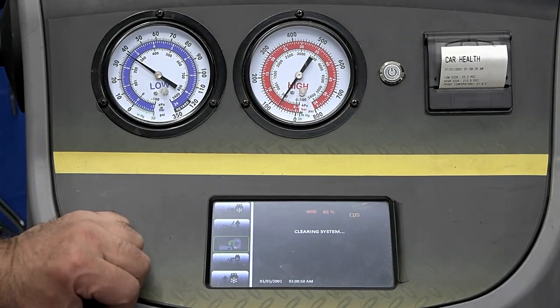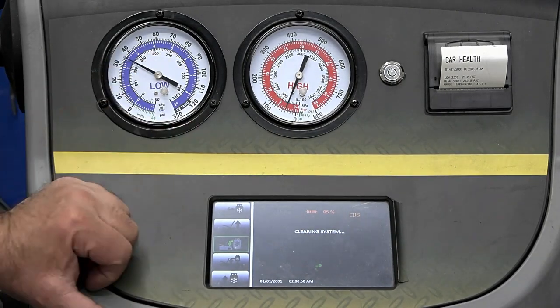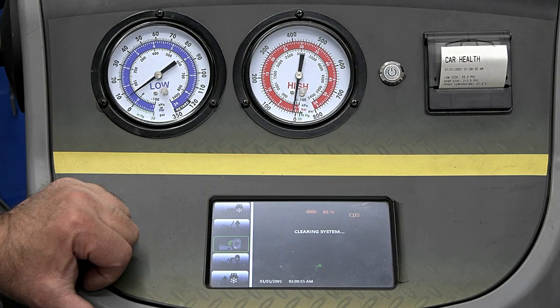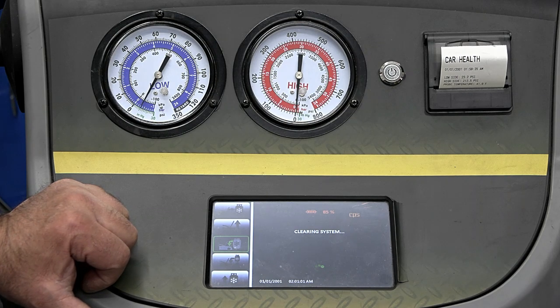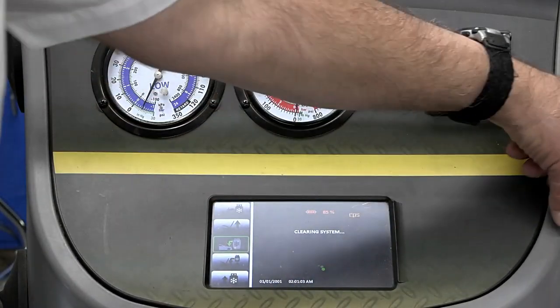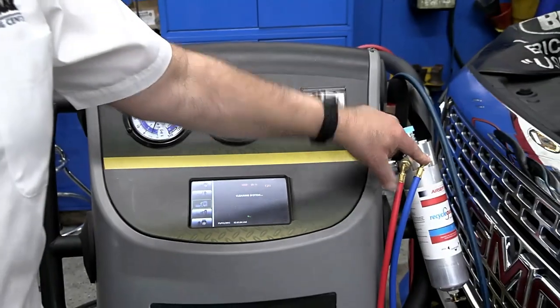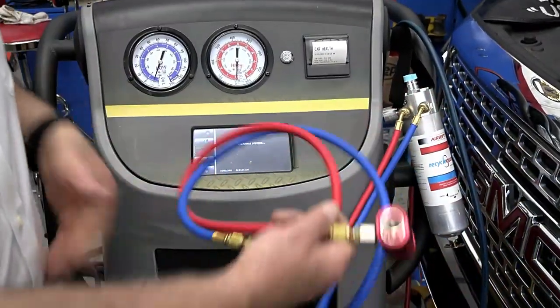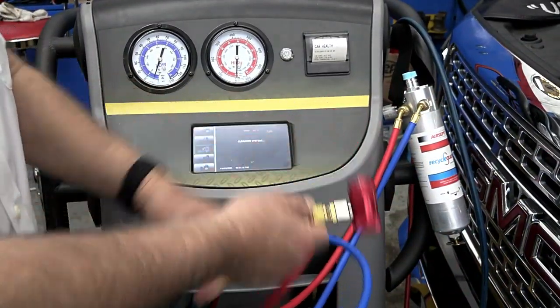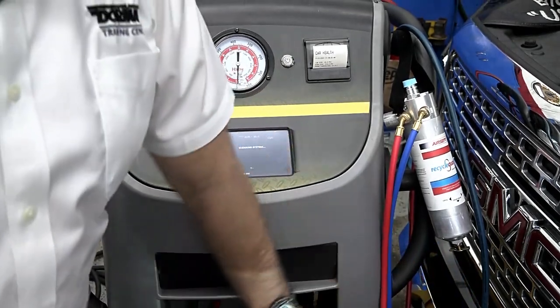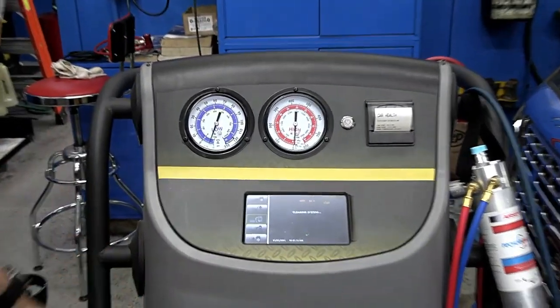So we're just going to go here, clearing the system. It's going to suck these hoses all the way down. You should always put your machine away in a vacuum. That way you can know if any of the line ends in the back of the machine, or if your couplers here maybe leaking at these ends, you always want to check that out. This is the proper procedure.